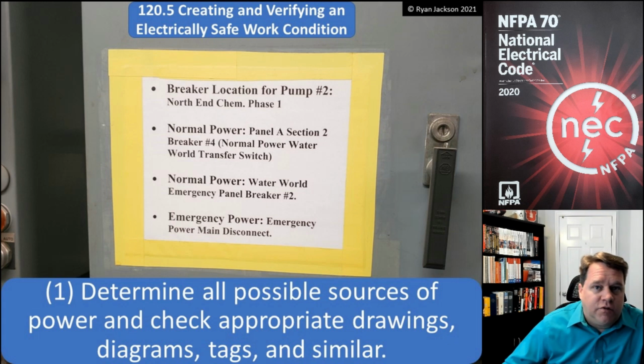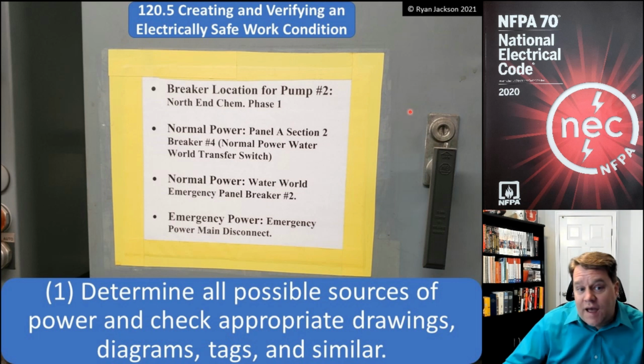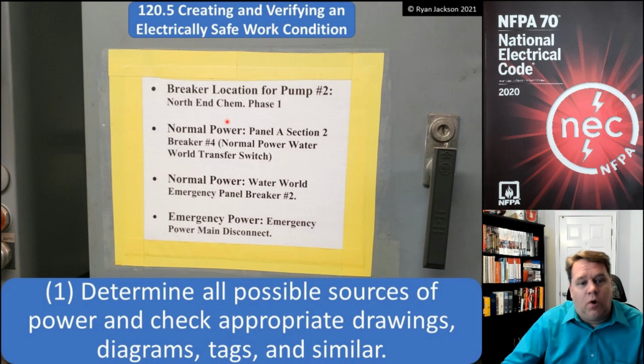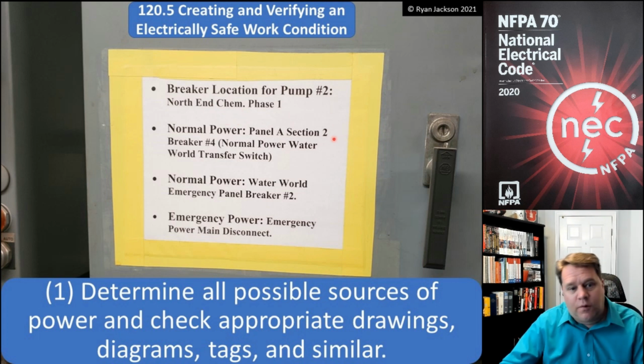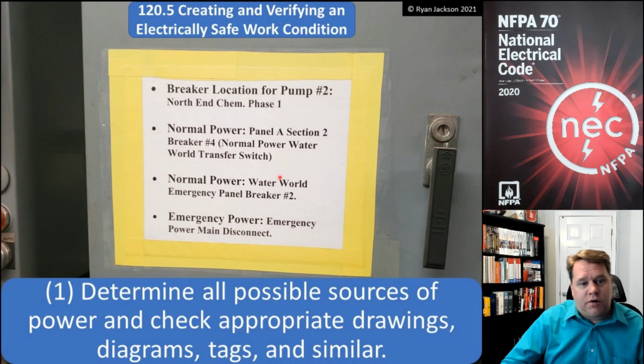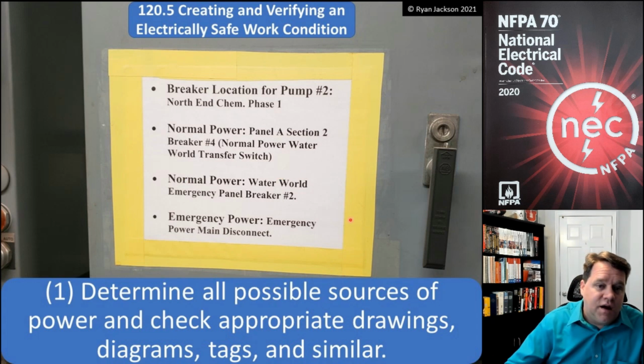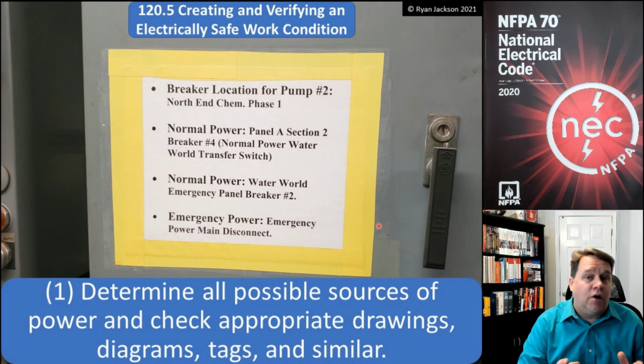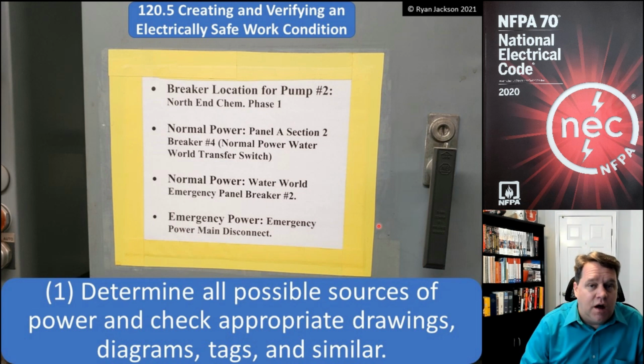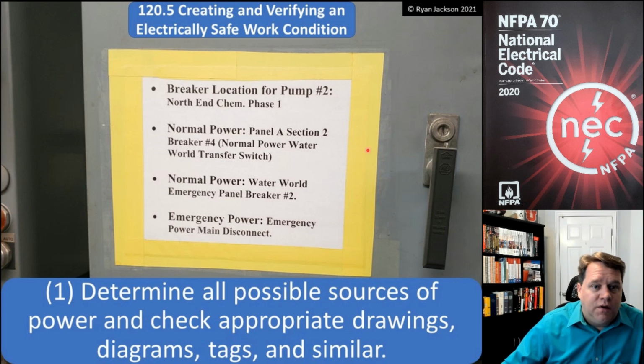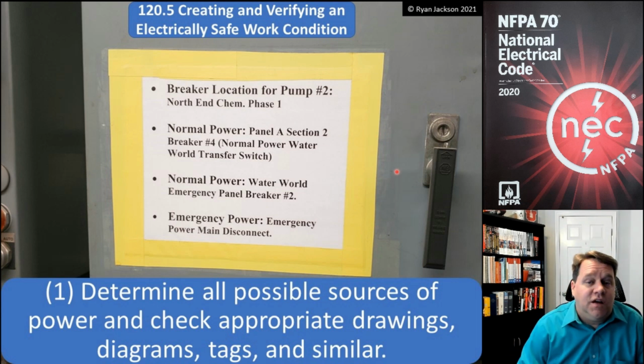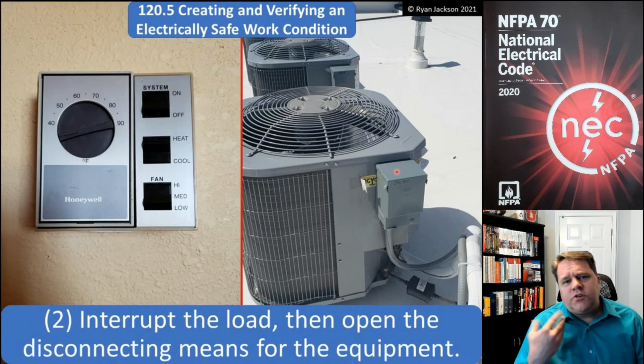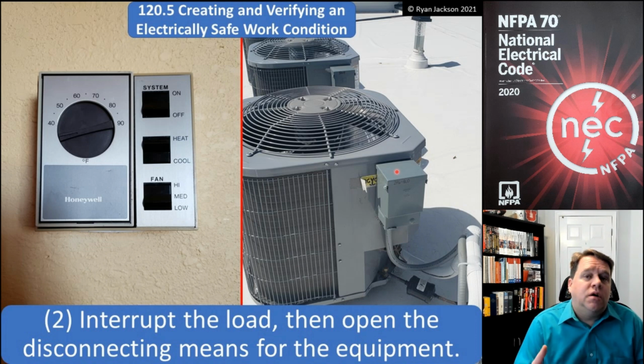This is at a facility where I teach, and shutting off everything for this equipment can be quite a task. It says, okay, breaker location for this pump is the north end, phase 1, normal power, panel A, section 2, breaker 4, and then emergency panel breaker number 2, and the emergency power main disconnect. So I love the fact that they've actually outlined exactly what needs to be de-energized in order to work on this equipment, because sometimes, again, it's not very easy.